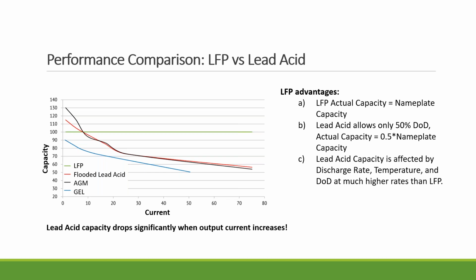Now, the one thing is about the capacity, how you read the capacity. So the lead acid usually tells you it's 200 amp hour or 400 amp hour rated, right? So that's an example, 200 amp hour. Typically you can really only get about half. So the nameplate is not the actual capacity; the actual is usually 50%. The LFP actual capacity is equal to the nameplate. So with 200 amp hour, you really can get 200 amp hour. And also the lead acid capacity can be more impacted by the charging and discharging rate and temperature.